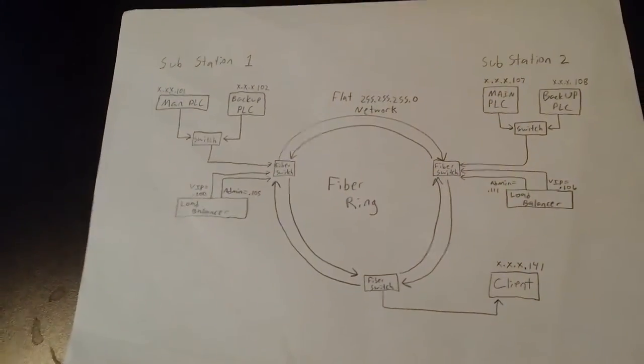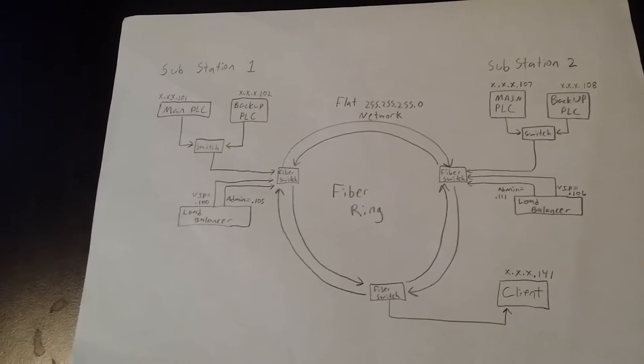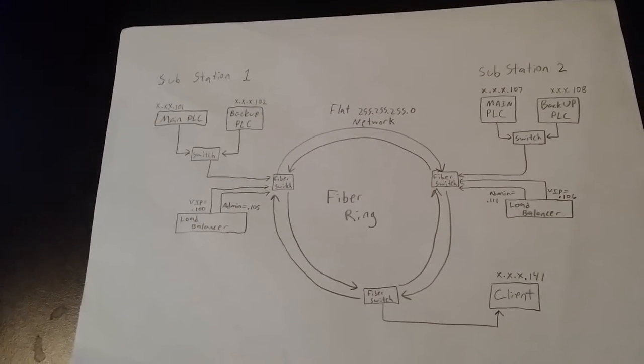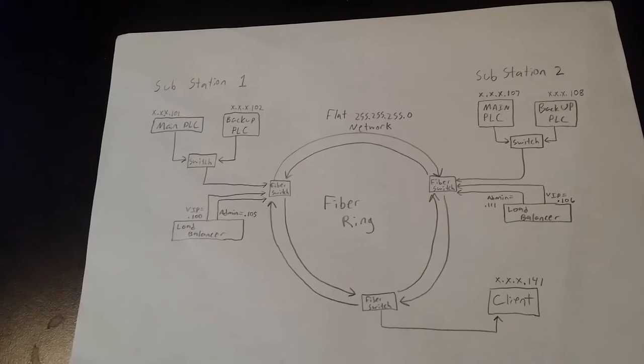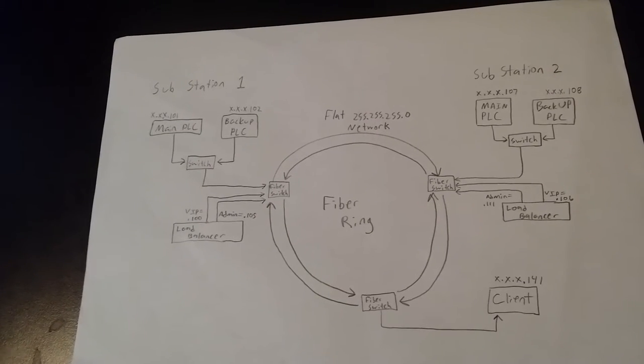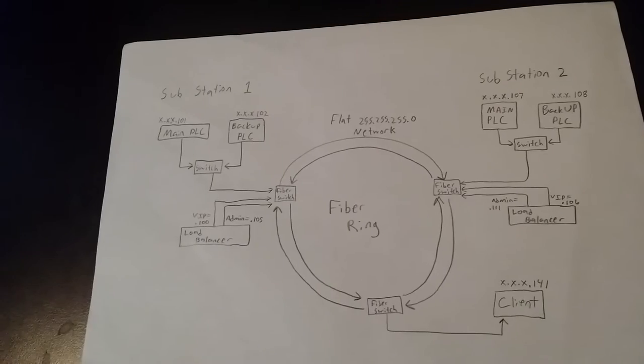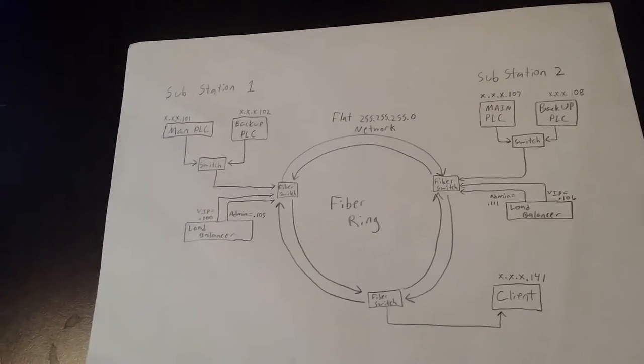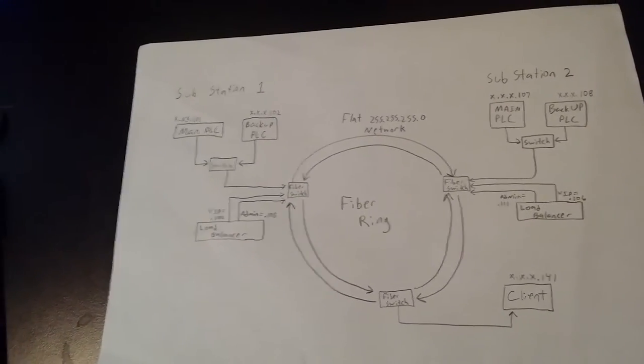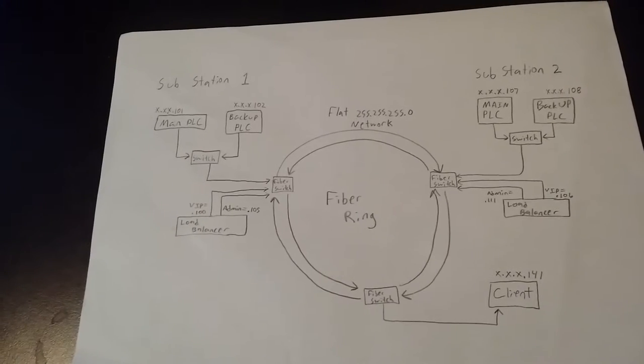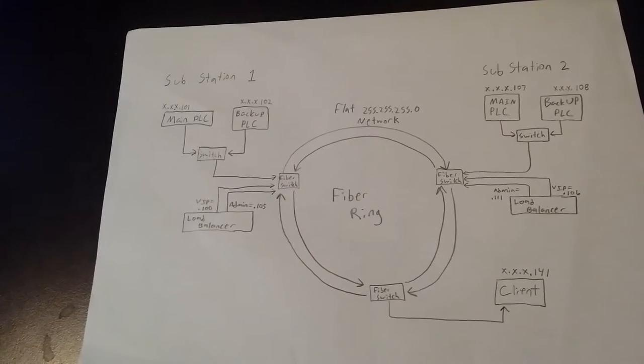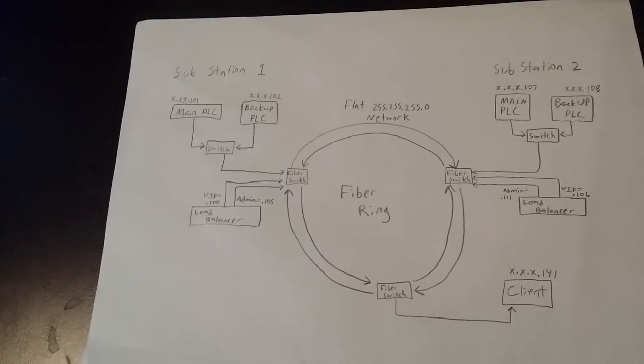So first off, why is this necessary? Because if you have multiple clients trying to access the primary PLC and it fails, what will the clients point to? If the secondary does not assume the failed PLC's network settings like IP address, then most clients cannot automatically change all their bindings and point to something else. That's supposed to be the PLC's job. For example, GE PLCs lack this basic functionality for some reason and would require this solution.